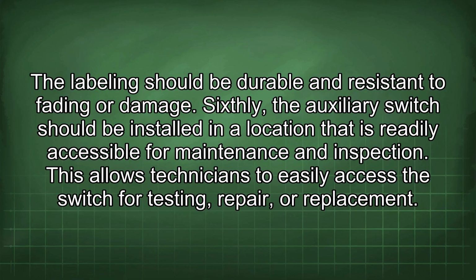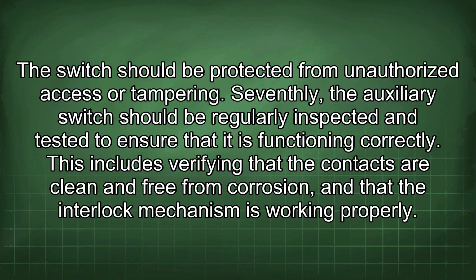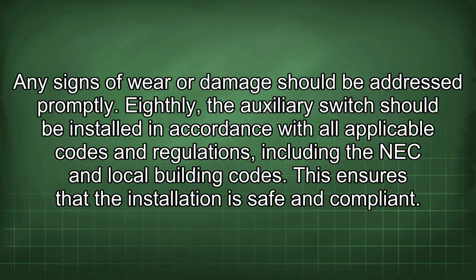This allows technicians to easily access the switch for testing, repair, or replacement. The switch should be protected from unauthorized access or tampering. Seventhly, the auxiliary switch should be regularly inspected and tested to ensure that it is functioning correctly. This includes verifying that the contacts are clean and free from corrosion, and that the interlock mechanism is working properly. Any signs of wear or damage should be addressed promptly.